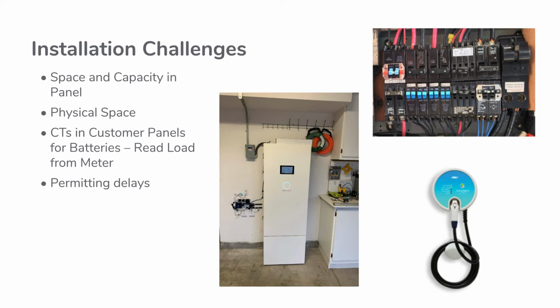In addition, we need physical space for the circuit, and the Sonnen battery takes up a fair bit of space in the garage. Additionally, those batteries need to know what the customer load is so they can accurately discharge, because currently the interconnection rules do not allow the battery to discharge to the grid.